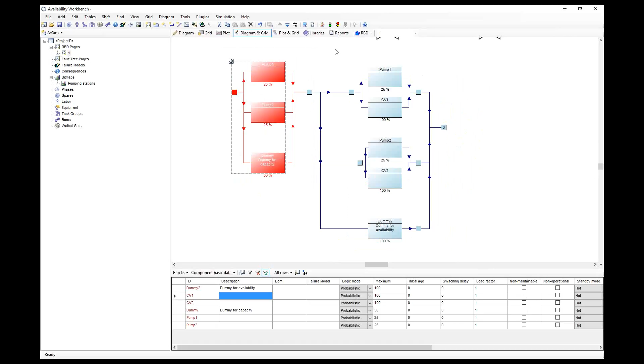I'm going to adjust this vote here to 3. Now I've captured the availability with this arrangement. If I lose a single pumping station, I'm no longer meeting my vote of 3. However, these are incapable of affecting capacity. So long as the vote number is met, I guarantee 100% capacity through my dummy block down here. This prevents this arrangement from ever influencing capacity. So I've captured both the capacity model with this arrangement, and the availability model with this arrangement. Okay, makes sense?